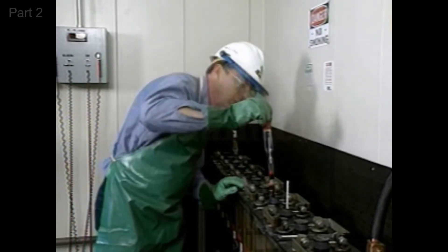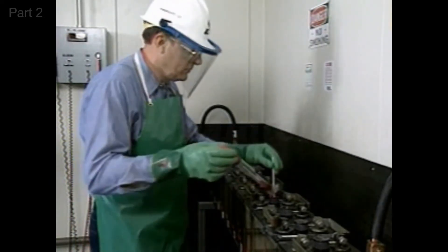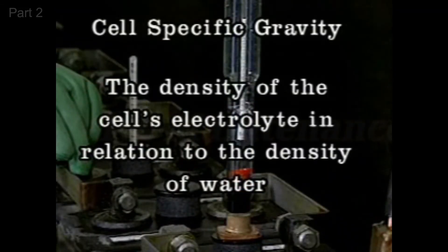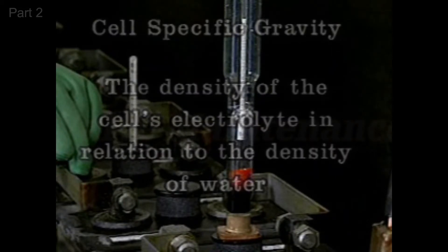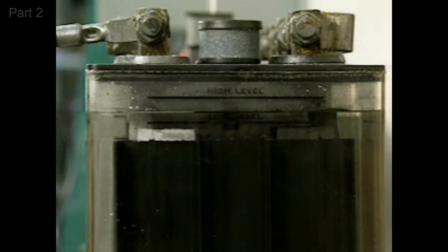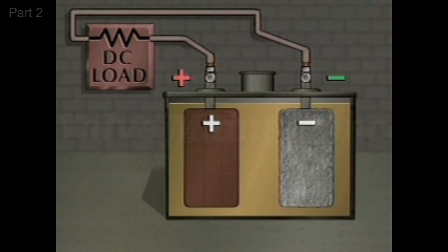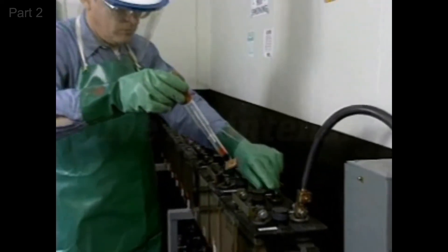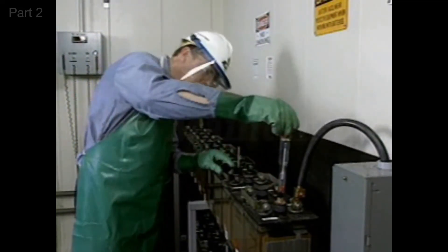Another indication of a battery state of charge is the specific gravity of the cells. The specific gravity of a cell is defined as the density of the cell's electrolyte in relation to the density of water. The electrolyte in a cell is composed of sulfuric acid and water. As a cell is discharged, sulfuric acid leaves the electrolyte and combines with the lead in the plates, decreasing the concentration of sulfuric acid in the electrolyte. So a test that reflects the concentration of sulfuric acid in the electrolyte will show the state of charge of that cell. That test is for the specific gravity of the electrolyte.